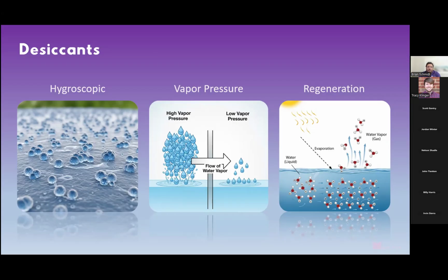So what do we do about regeneration? A desiccant will absorb moisture, and then do we just throw it away? No, we need to regenerate it. So we do that by applying heat. We do this differently than a solid desiccant system. Again, I'll show that here in just a little bit. But essentially, the takeaway is that we need a little bit of heat to evaporate that moisture from the liquid desiccant. Liquid desiccants then can thermally cycle infinitely, right?